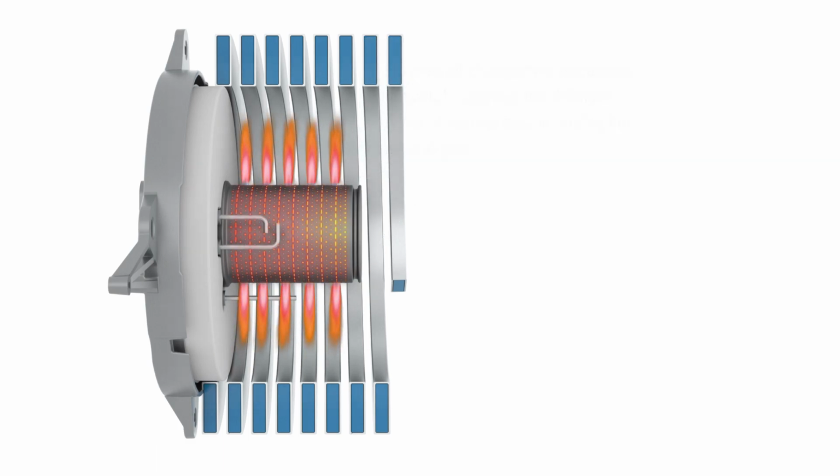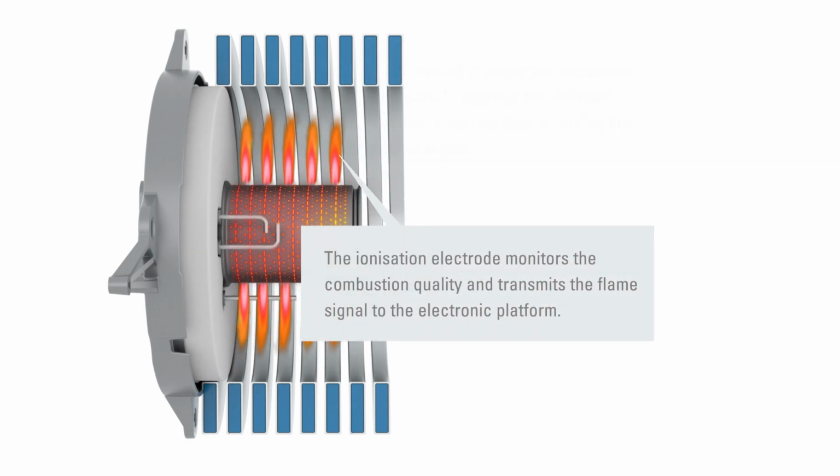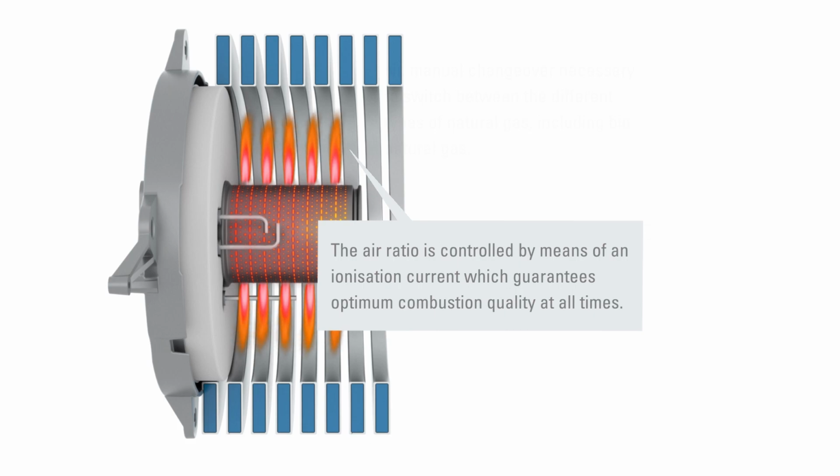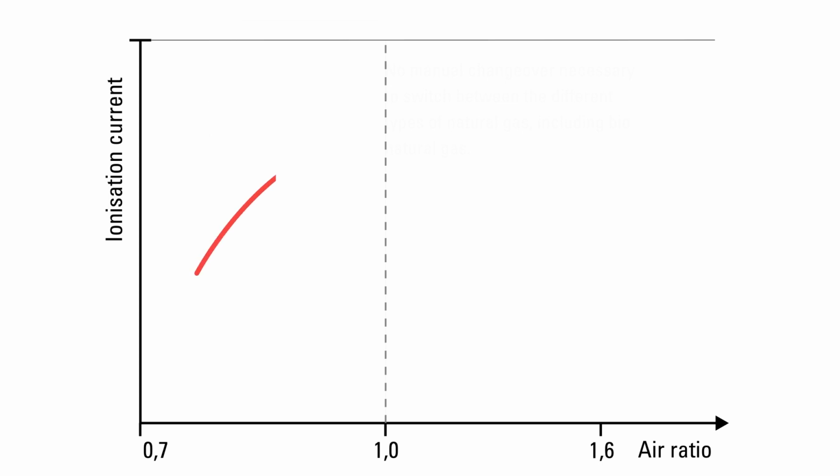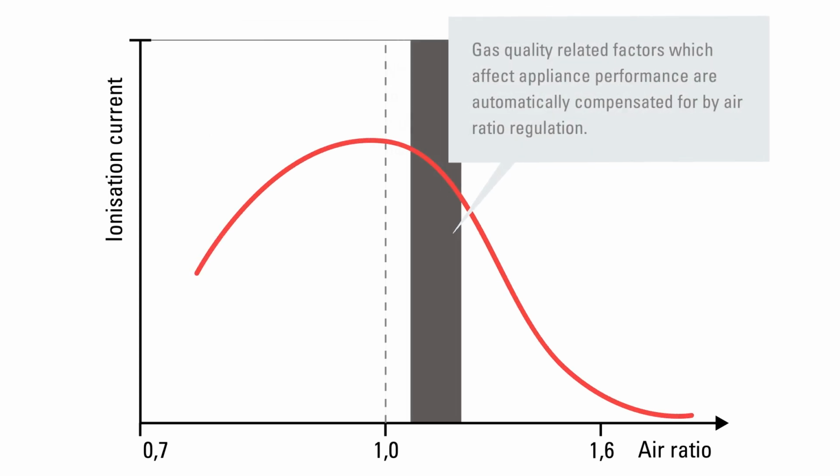The self-calibrating combustion controller can also detect fluctuations in the gas quality and compensate for this automatically by adjusting the gas-air mixture. This means that combustion remains permanently stable and environmentally responsible even with fluctuating gas qualities, yet efficiency remains consistently high, as does the operational reliability. The ionization electrode of the Lambda Pro Plus provides the necessary unadulterated readings directly from the flame.